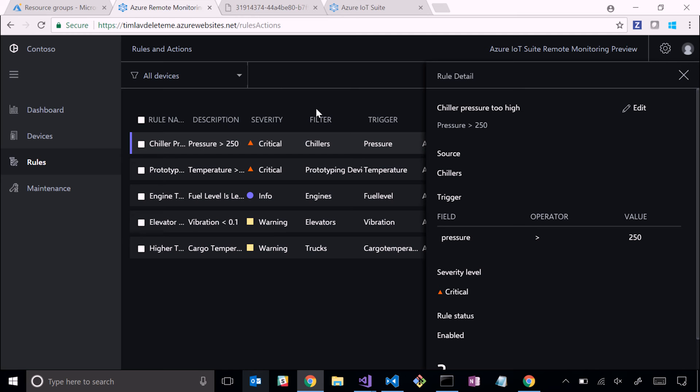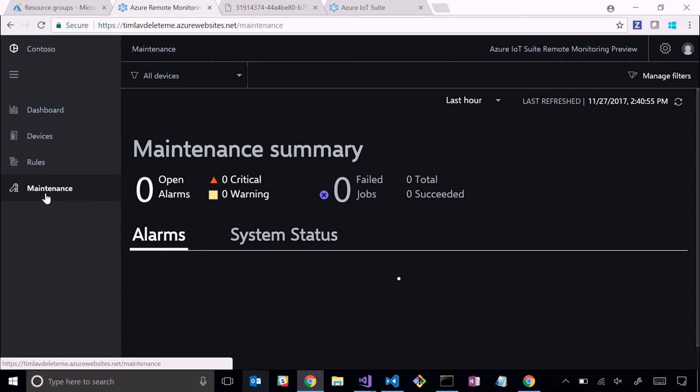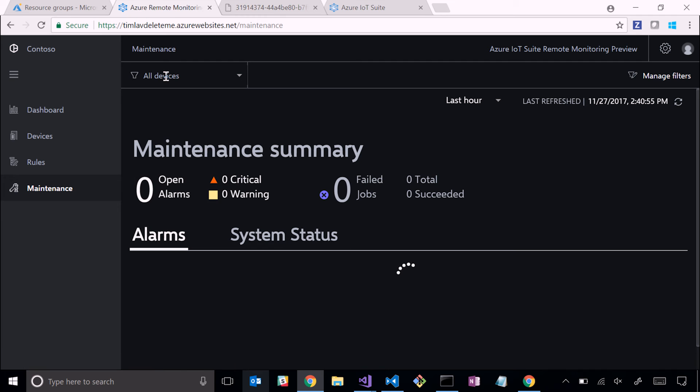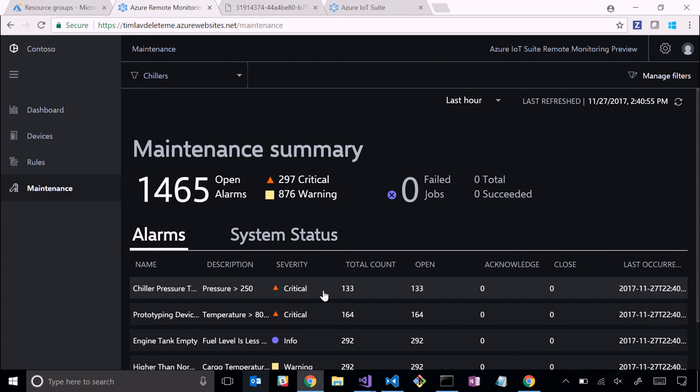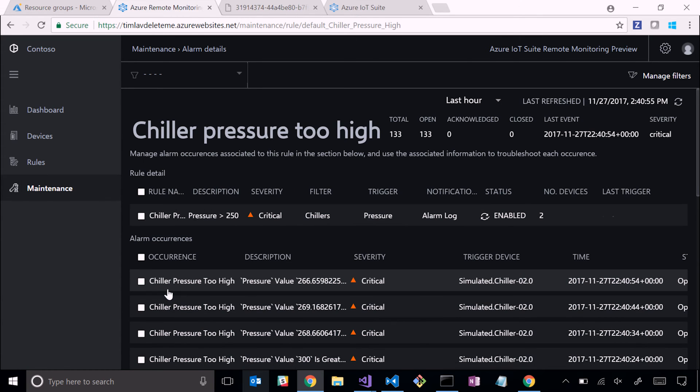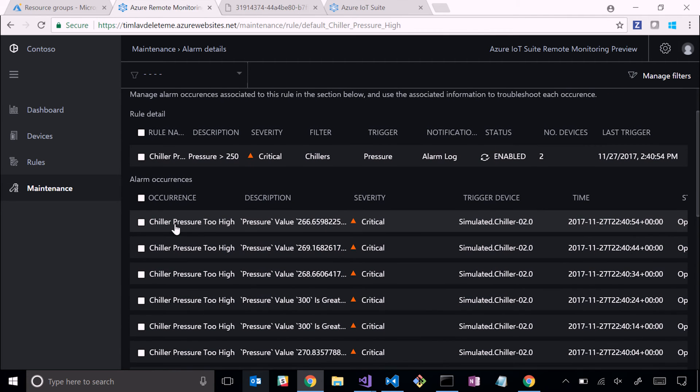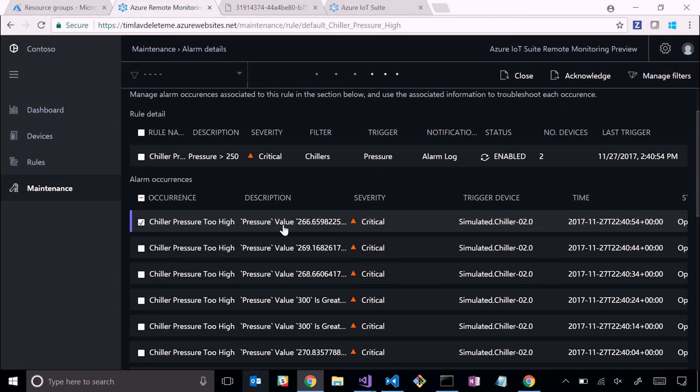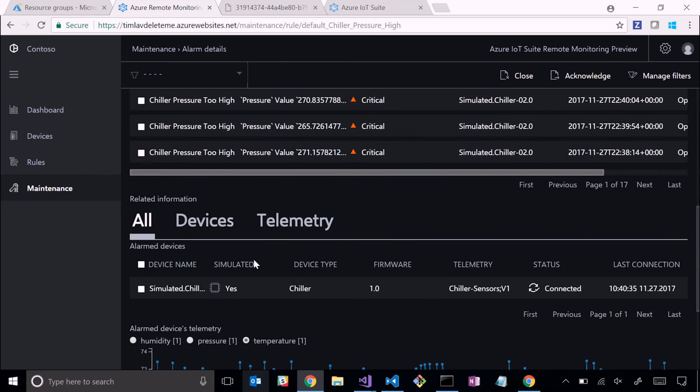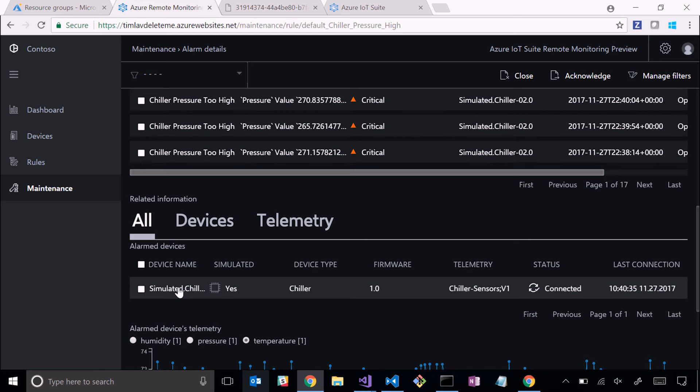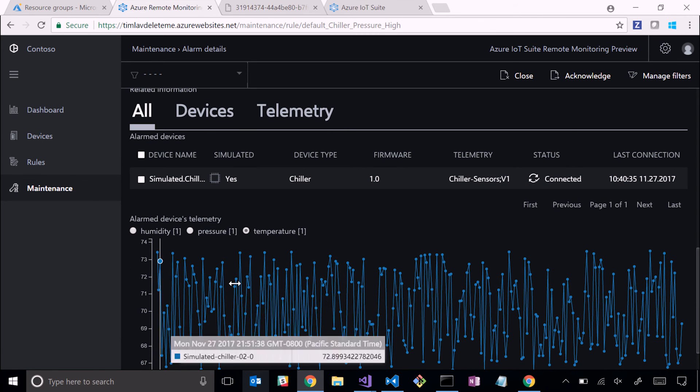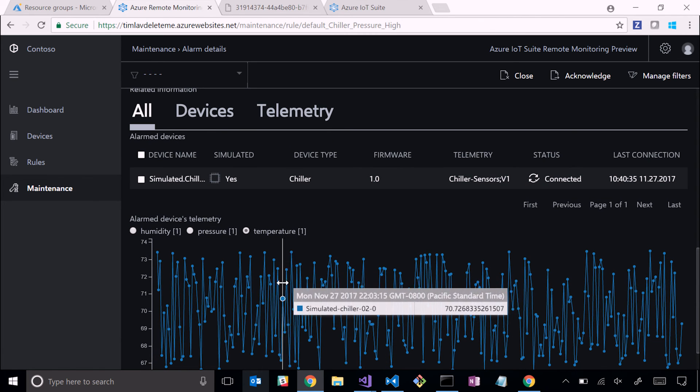You have this pattern - ingesting data, determining insights using the rules, taking action. Let me show you an example with that dashboard on how to take action. We were just looking at this particular rule. Let's go over to maintenance and filter this to just chillers. Here you see we have an alarm for this chiller pressure rule. If we click on this, we'll see a number of occurrences of that alarm happening. If I wanted to acknowledge that alarm, I could. When you acknowledge, you're basically saying I've seen there's an alarm, I'm looking at this alarm. Here we have the device that's generating these alarms. This device is in error - it's triggering that pressure alarm consistently.